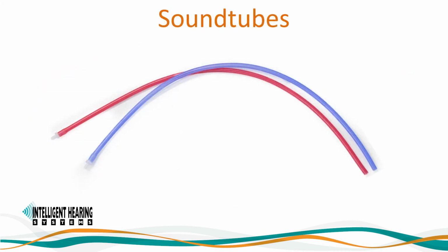Always inspect the sound tubes and make sure that there are no cracks on the tube that may be causing sound leakage, thus attenuation of sound and decibel losses. Make sure that the tube length used on ER insert earphones is the standard ABR length. Do not connect additional tubing to the standard ER insert earphones. If different tubing is used, then you must remove the current tubing and replace the new tubing directly on the speaker boxes of the ER insert earphones.